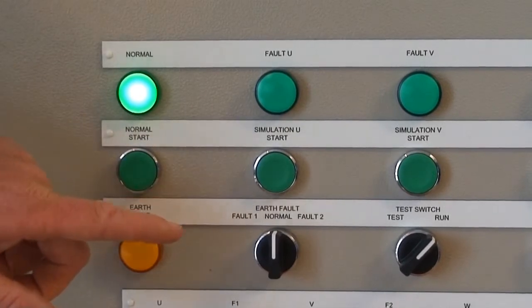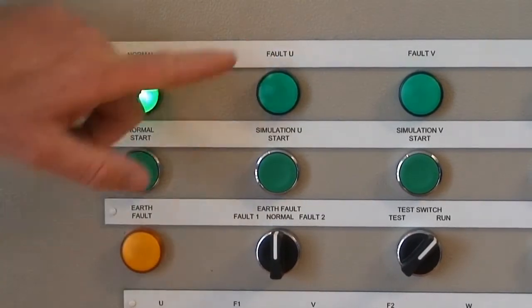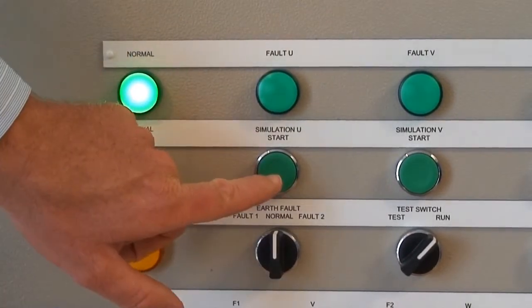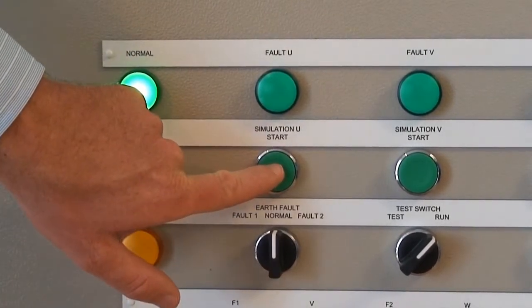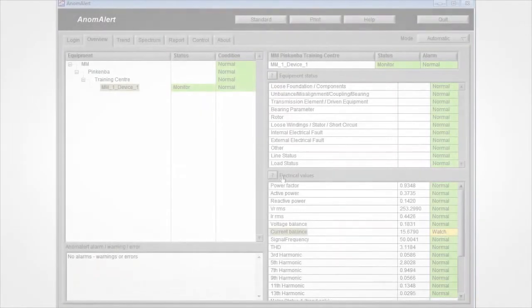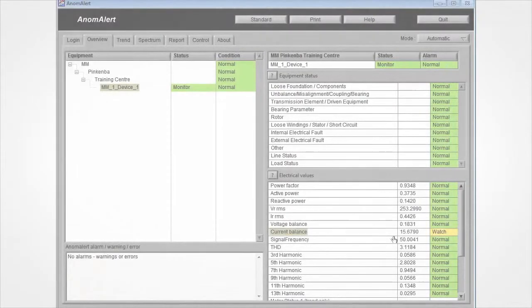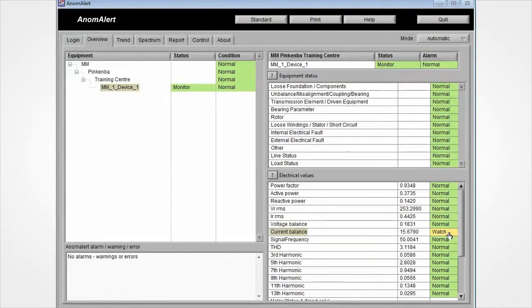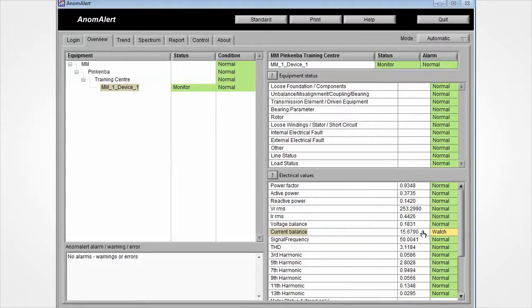To demonstrate, the device will now introduce a turn fault into U phase. Back on the overview page, it can be seen that the Anomalert software has detected the turn fault introduced earlier and has indicated this with a watch.